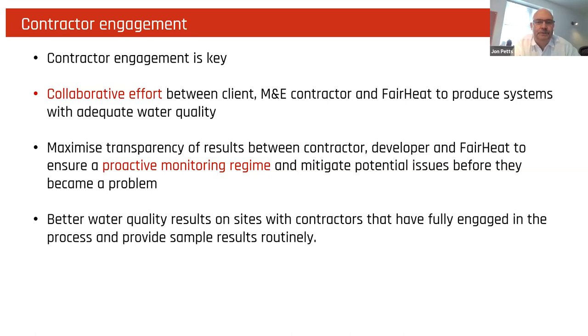So if we get a decent brief to start with, then we look to the contractors coming up with detailed method statements of how they're going to carry out their flushing processes and ongoing water treatment. And we study those method statements in detail. FairHeat give us assistance on those, looking at the detail, commenting if anything needs to be tweaked. Basically the key there is getting the systems right to start with. If it goes off on the right foot, systems are flushed correctly and the water treatment regime is initiated at the right time as soon as systems are filled, it's a lot easier to keep them within limits rather than having a problem and trying to dose, shock treat or reflush in the worst case.